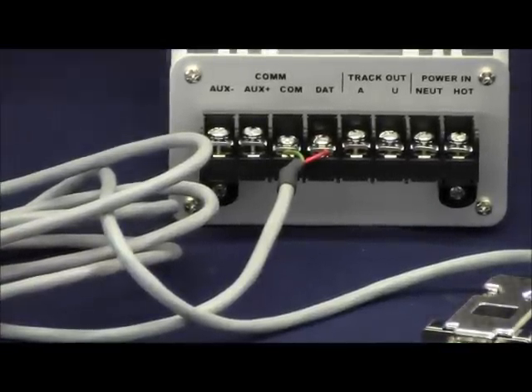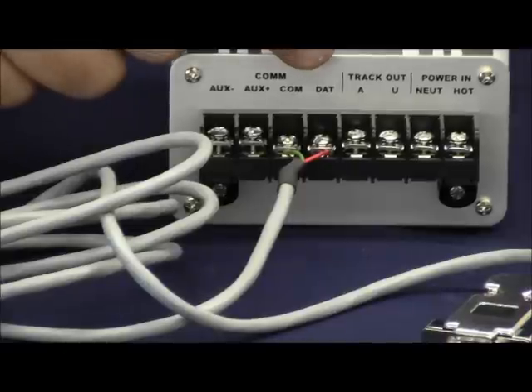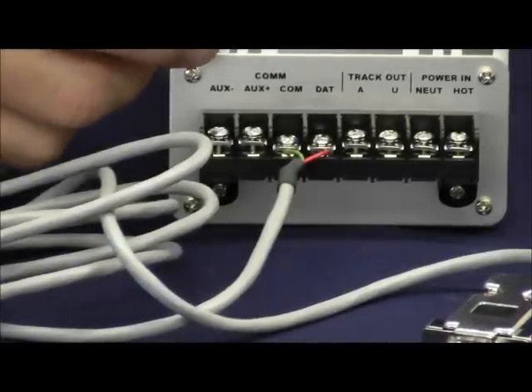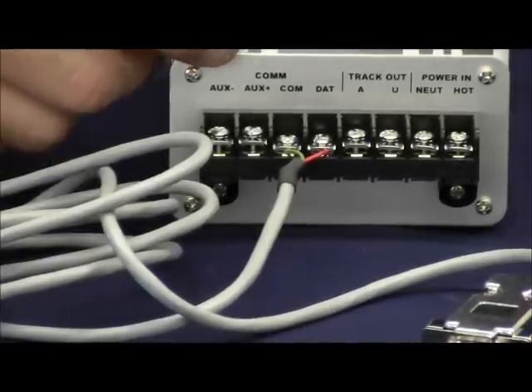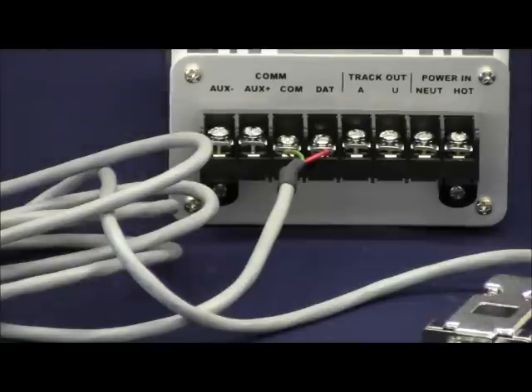As you can see clearly in the picture now, we have COM and DAT. On this side it says AUX plus and AUX minus. Those terminals are not used. Do not connect anything to the AUX plus or AUX minus terminals on a TPC.